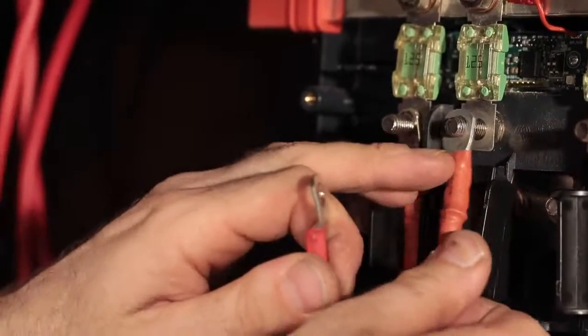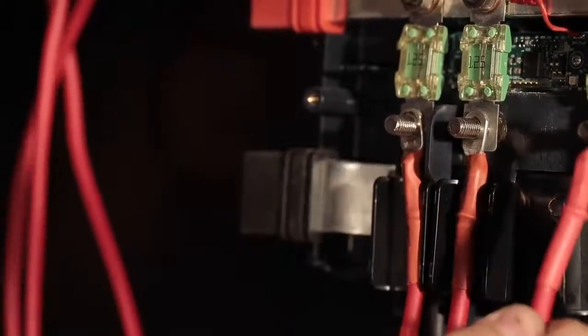Now in this case, we've already put our mega fuses over the top. Once the mega fuses are installed, which are appropriately rated for the 48 volt system, you can get them in 24, 36 and 48 volts, you can then put the battery positive cables on.